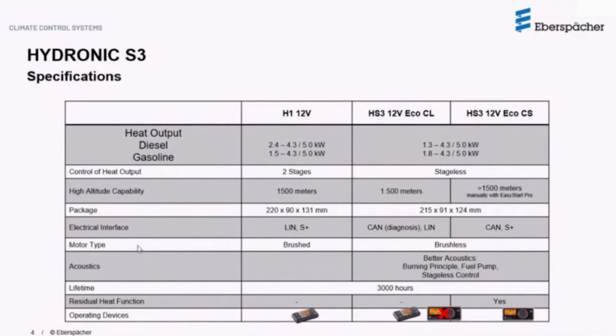The motor type is now brushless on the new version of the heaters compared to the first generation. From an acoustics point of view, this heater has far better acoustics, achieved due to a much better burning principle. We now have variable output, so the heater doesn't have to switch between high, low, and medium settings. The fuel pump has been modified to make it a lot quieter, along with stageless control. All of this achieves much quieter operational noise.